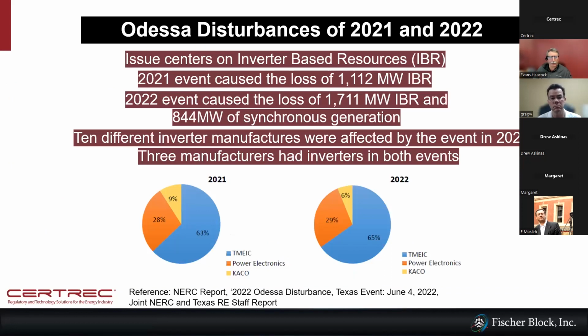I mentioned this at the beginning: there were two Odessa disturbances, one in 2021 and then also in 2022. The main reason they're called the Odessa disturbance is because they had transmission line issues in the Odessa area of Texas that caused major large-scale outages from inverter-based resources, due to the type of faults and the inverters not necessarily responding incorrectly, but maybe over-responding to some degree. As you can see, in 2021 they lost a little over 1,000 megawatts of inverter-based resources, primarily solar type. Then in 2022, the number was up a little bit, from 1,100 to 1,700 megawatts. So a lot of disturbance issues, and this is what definitely got NERC's and ERCOT's attention during these events. That was a lot of power lost at one time.